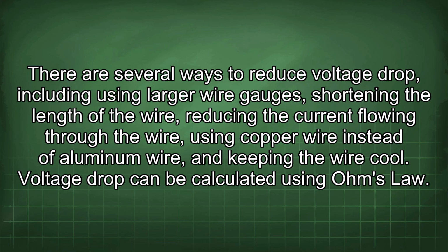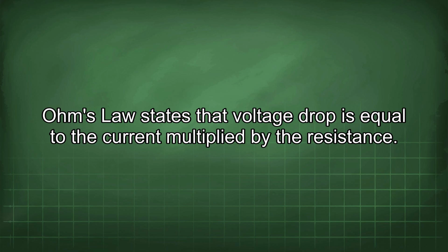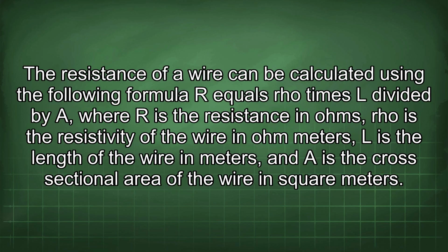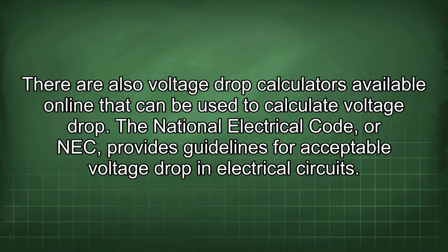Voltage drop can be calculated using Ohm's law. Ohm's law states that voltage drop is equal to the current multiplied by the resistance. The resistance of a wire can be calculated using the following formula: R equals ρ times L divided by A, where R is the resistance in ohms, ρ is the resistivity of the wire in ohm meters, L is the length of the wire in meters, and A is the cross-sectional area of the wire in square meters. There are also voltage drop calculators available online that can be used to calculate voltage drop.